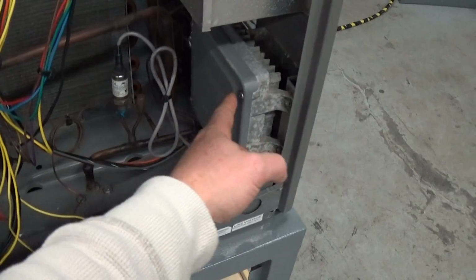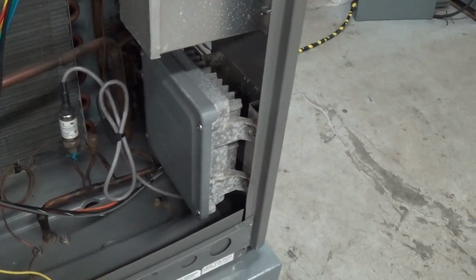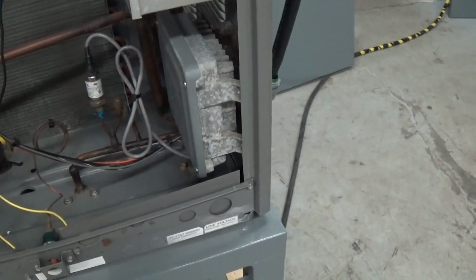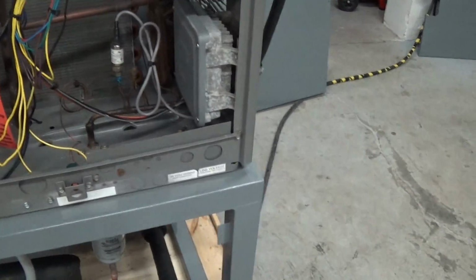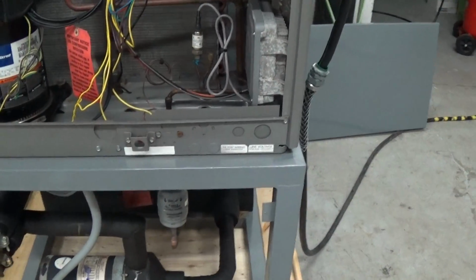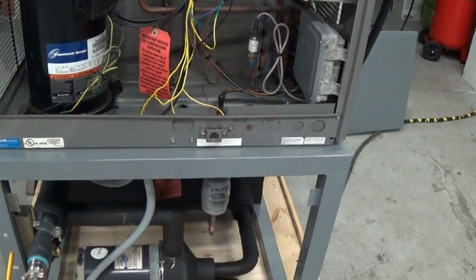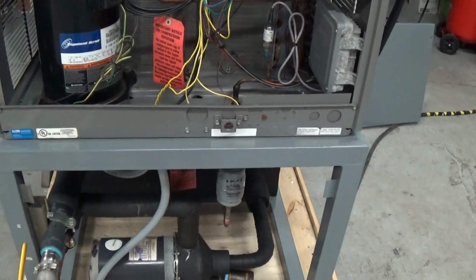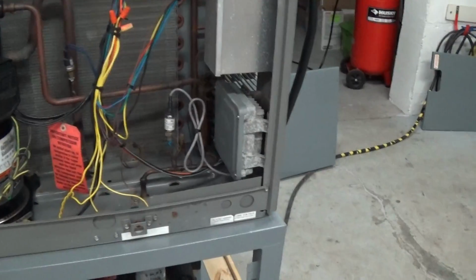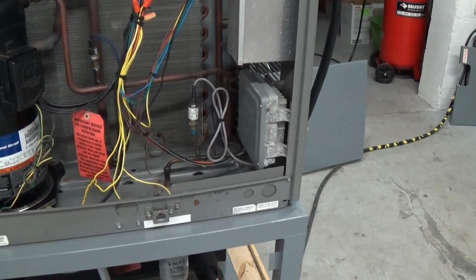This here is what we call a P266 fan speed control. That's part of the low ambient package, which allows this to run outside even in the cold weather. It controls the fan speed based on pressure, something that you need for colder weather climates.